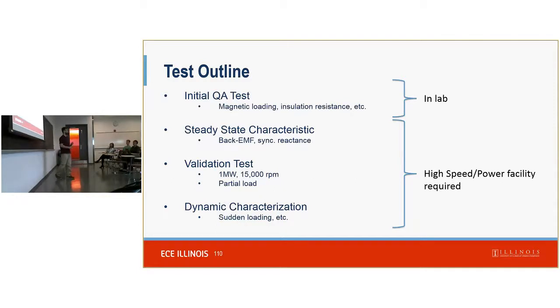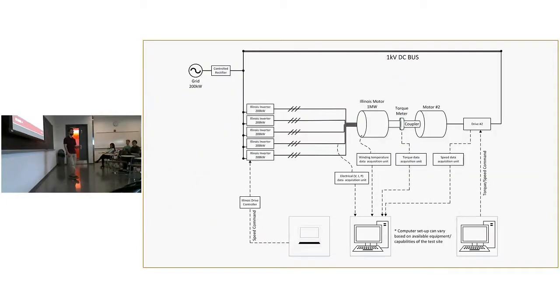And so the plan is to go to UTAS, or United Technology Research Corporation, outside of Chicago, and they have a lab where we will be doing testing once the final rotor is complete and our motor is ready to actually be tested. So we've already completed much of the quality assurance testing, and so we're waiting for the high-speed, high-power facility at United Technologies. And to drive it there, we will be using drives that are slightly modified from the drive from this Boeing 787. And so that test should go to the full megawatt, full 15,000 RPM, and we'll learn a whole lot by doing this test once it gets completed.